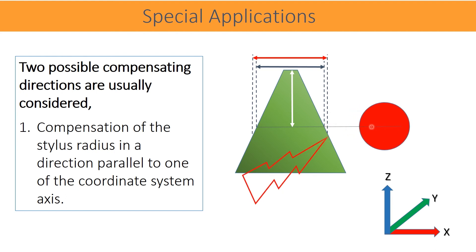If we probe the point in the axis direction, the point compensation is done in the axis. But still we cannot reach the point by correction exactly where it is supposed to be. This happens because the axis and the slant cone edge are not parallel and again a cosine error is the result of it and the measurement error is the result.